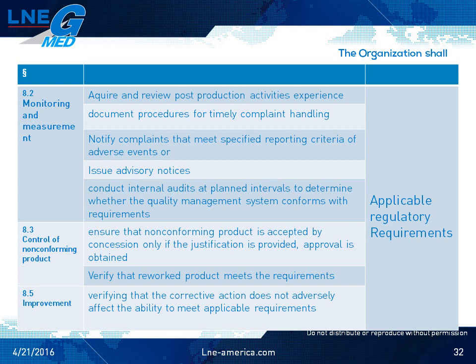The section dedicated to measurement, analysis, and improvement adds specific provisions for post-market monitoring, including vigilance. The new wording emphasizes the provisions preventing the placing on the market of products that are non-compliant with regulations. A key point to identify is the new explicit objective for internal audits, which shall be conducted at planned intervals to determine whether the quality management system complies with applicable regulatory requirements.